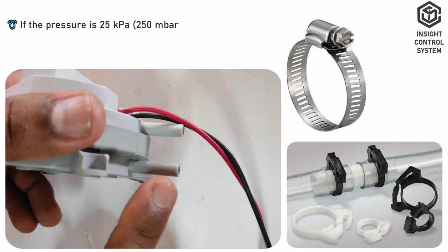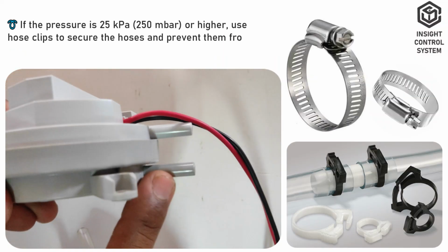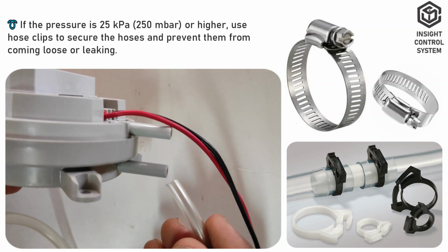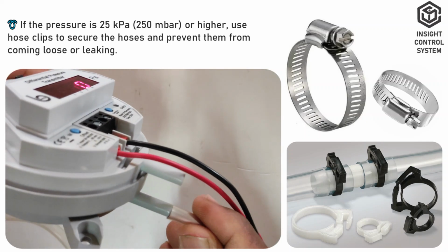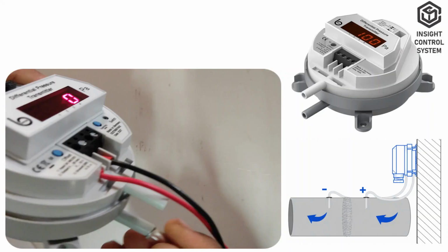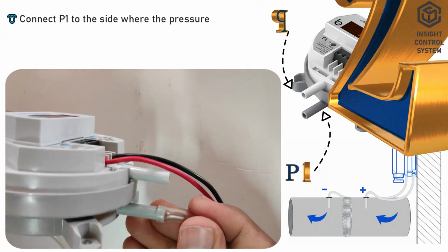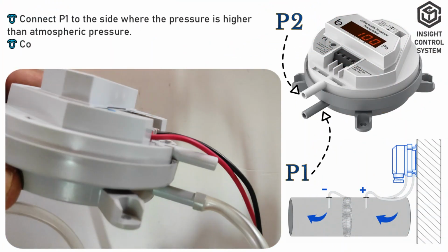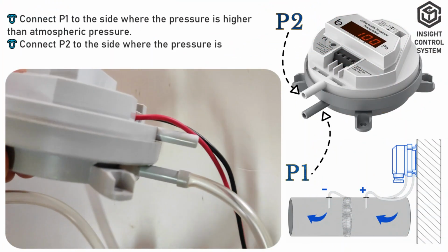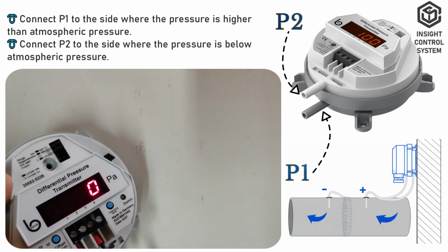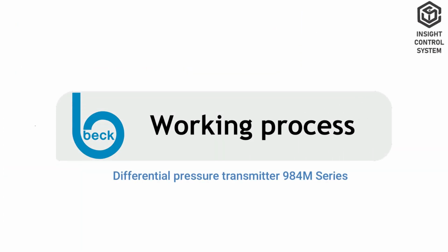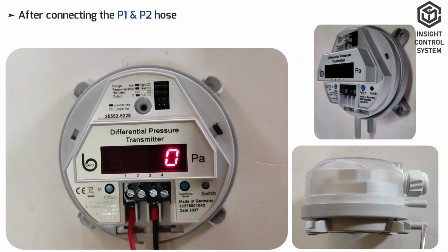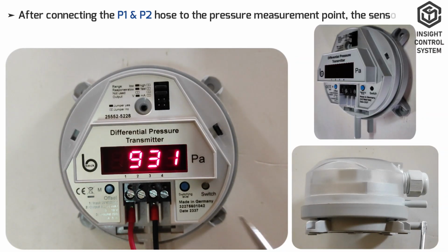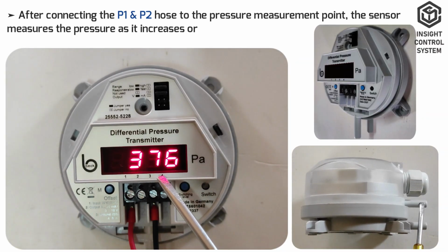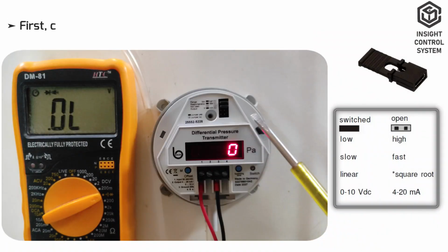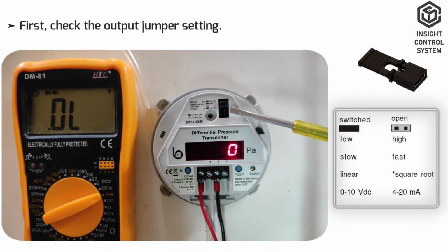If the pressure is 25 kilopascals or higher, use hose clips to secure the hoses and prevent them from coming loose or leaking. Connect P1 to the side where the pressure is higher than atmospheric pressure. Connect P2 to the side where the pressure is below atmospheric pressure. Working process. After connecting the P1 hose to the pressure measurement point, the sensor measures the pressure as it increases or decreases. First, check the output jumper setting.